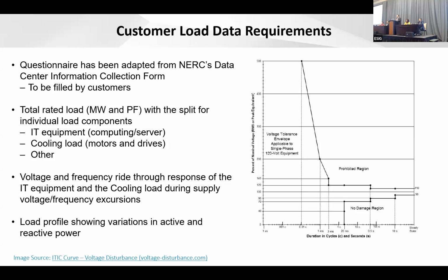This is very important because we're used to serving lagging power factor loads, but now we're learning these data centers can be leading. Planning for a 0.95 lag power factor 1 gigawatt load versus a 0.95 lead 1 gigawatt power factor load is a very different beast—it can determine whether you'd want a shunt capacitor bank or a shunt reactor bank.